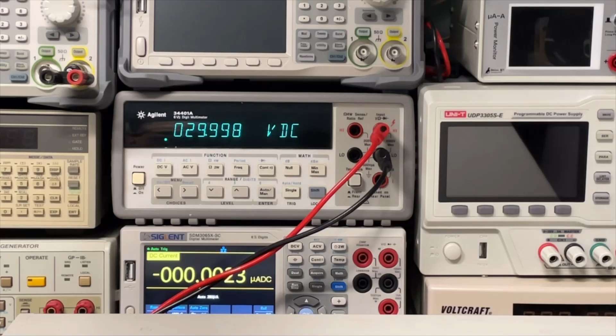Okay, pretty cool, even the calibration procedure still worked. For the overvoltage calibration, you really need to remember to pull your plugs, because if you don't, it disturbs the measurement and it will fail, and you need to do it all over again. So you need to do it right the first time — that's the only thing I found out, because it says error and then you're kind of stuck. But then you just start all over. The saving takes almost 10 seconds, and then you're waiting, but in the end it stores the values.